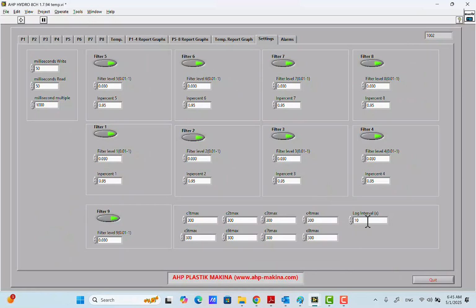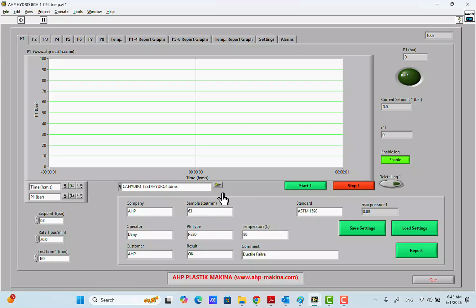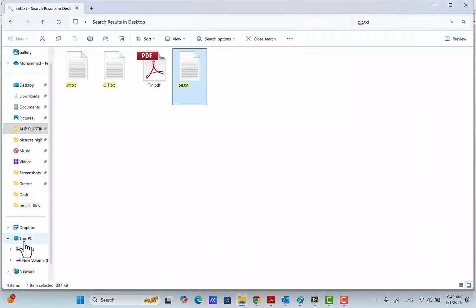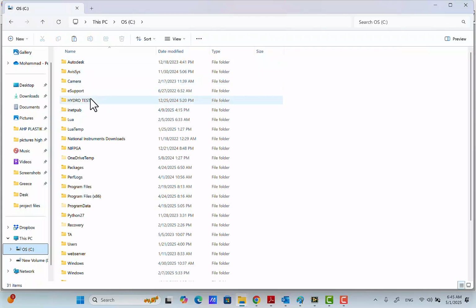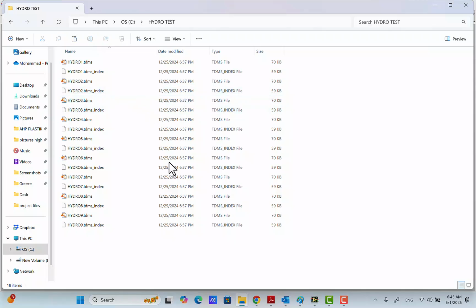In this case, you can set the log interval for the software. When it is set to 10 seconds, it means that every 10 seconds the computer saves data in a folder. Here you see the folder name, it's in root C, and the folder name is Hydrotest. Every 10 seconds the software saves data for each station in this database file named hydro.tdms.